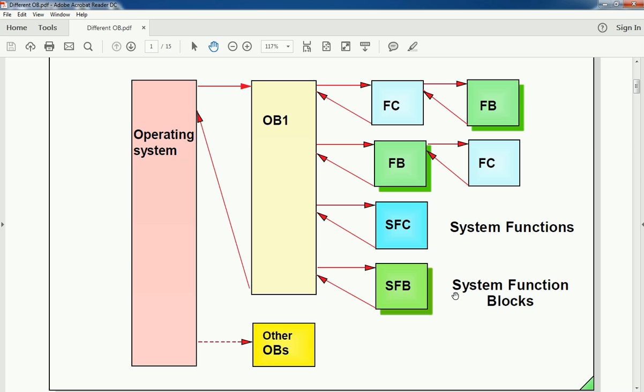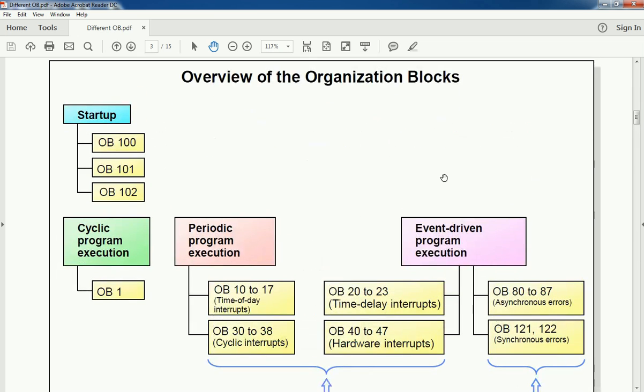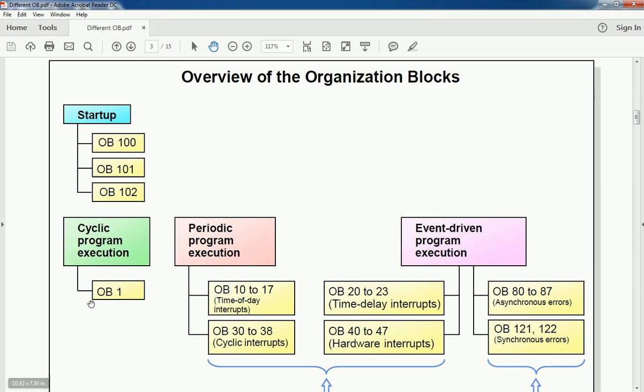Now we will see the overview of organization blocks. First, startup OBs: OB100, OB101, and OB102. These are the startup OBs that execute when the PLC is going from Stop mode to Run mode. The startup OB will execute only once, and the logic developed in it will execute only once when PLC goes from Stop to Run. OB100 is a warm restart, OB101 is hot restart, and OB102 is cold restart.